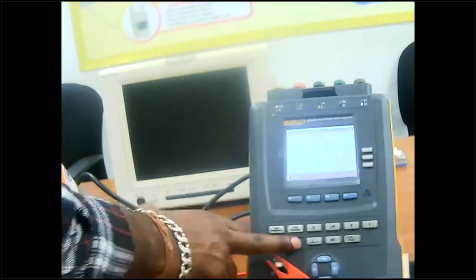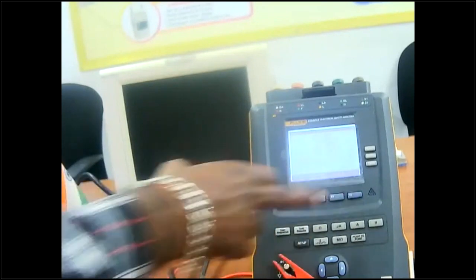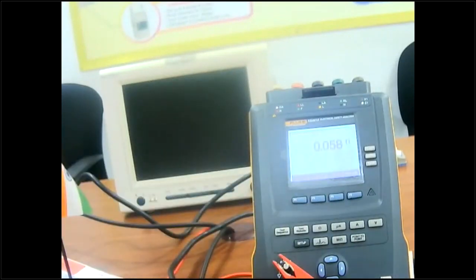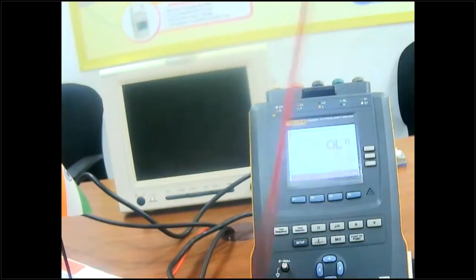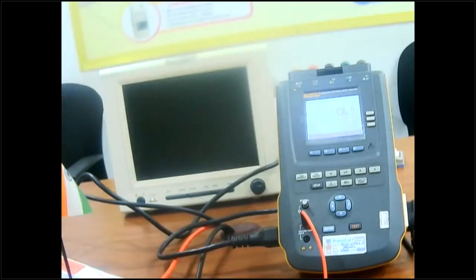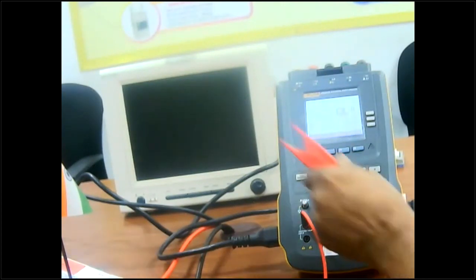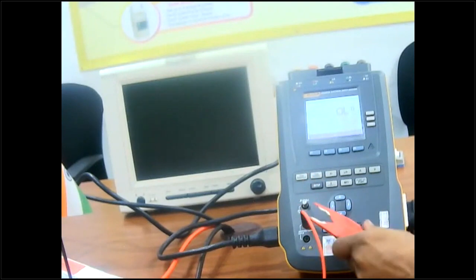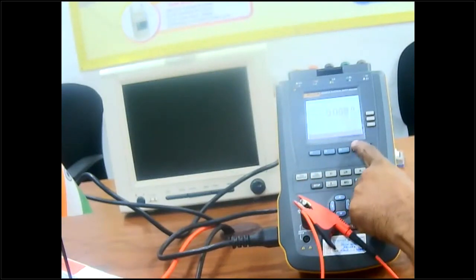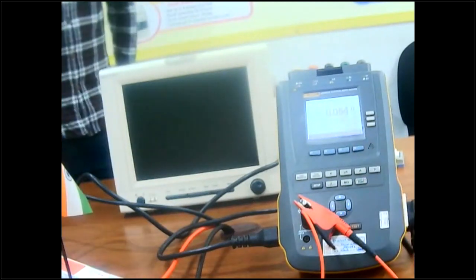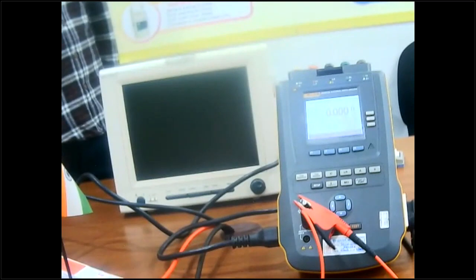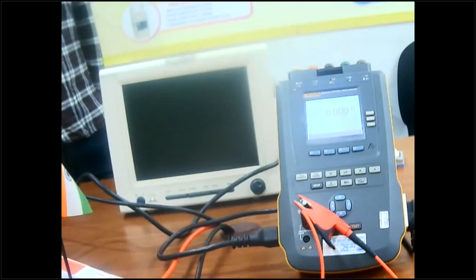We have set the test standard as 62353, and we are going to start the measurement with ground wire resistance. Before that, we first need to do the leads zeroing, because the leads we are using have a built-in resistance. So we have to zero the leads first. There is a null post available on the equipment. We put the lead on that, then press the F4 button and press zero to do the test. You can see it is showing 0.00 ohms right now.